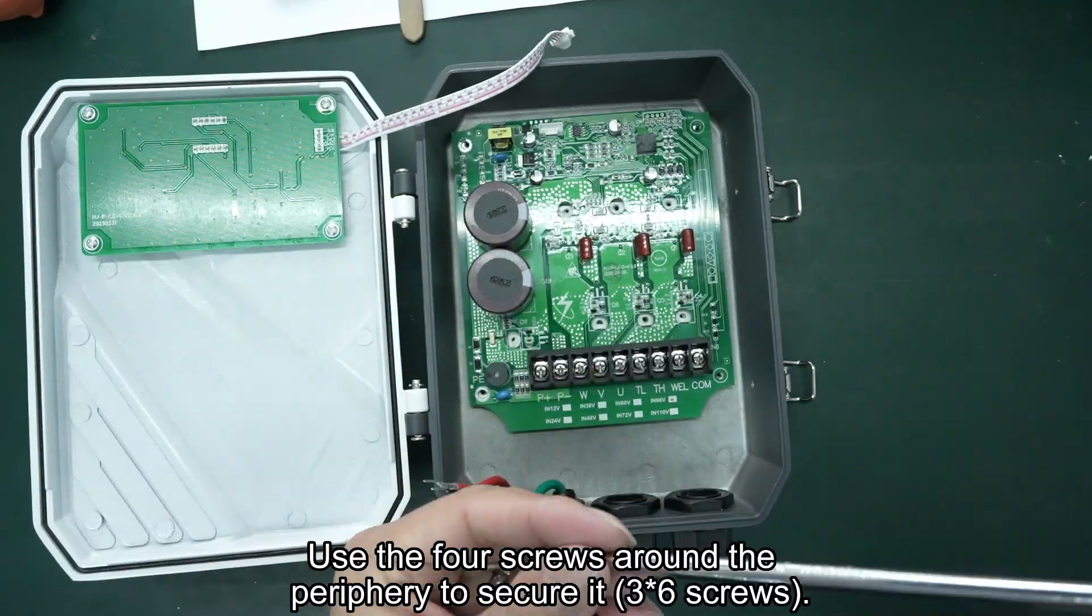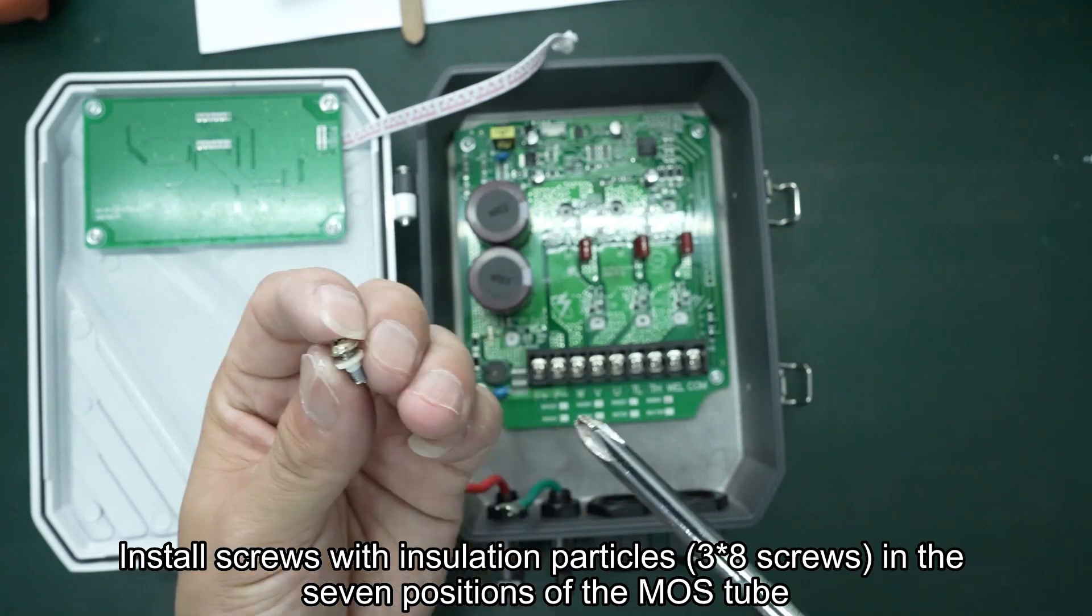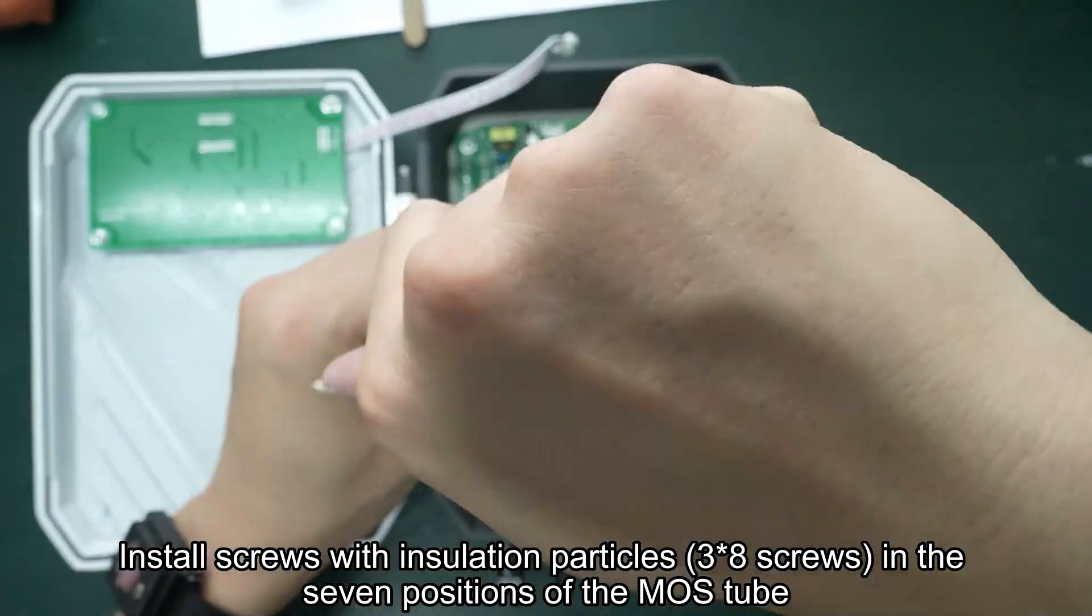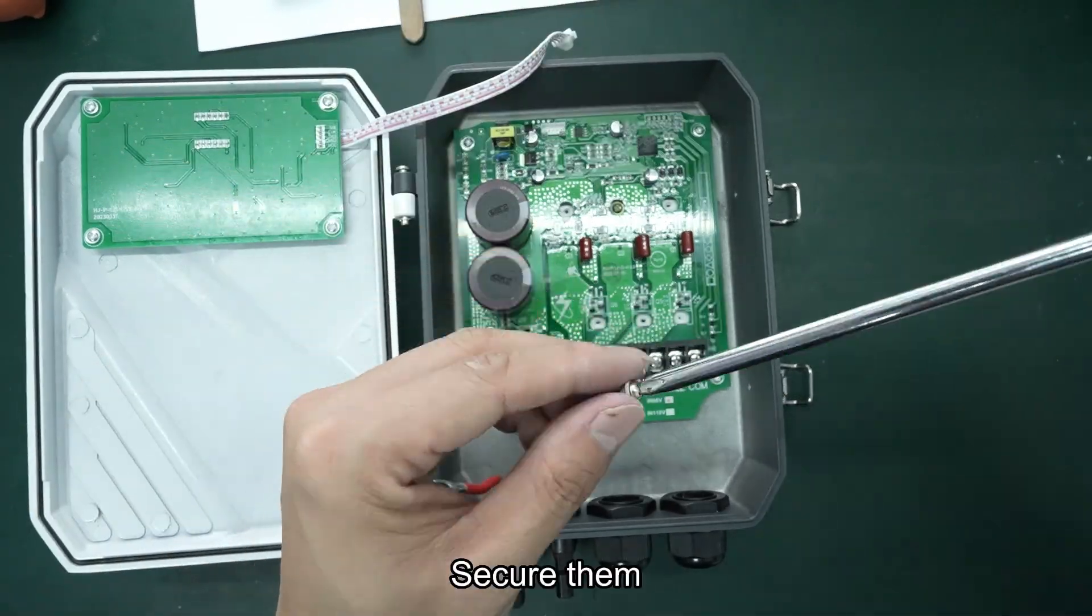Use the four screws around the periphery to secure it. Tighten the screws diagonally. Install screws with insulation particles in the seven positions of the MOSFET. Secure them and ensure the screws are covered with insulation particles. Confirm all screws are properly secured without omissions.